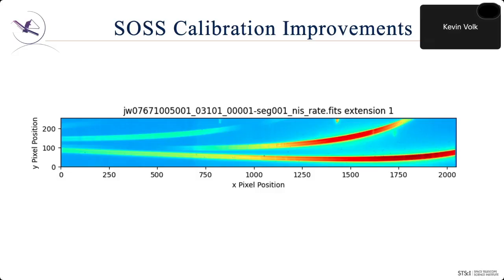This is what the spectra look like when you take a spectrum in this mode, just to show you. We've got several spectral orders on our detector. The first order is the one at the bottom, so that covers most of the wavelength range. Then order 2 is up above it and covers the short wavelength range from about 0.8 to 0.6 microns. And in this case, you can actually see, if you have good screen resolution, H alpha is here. So then you have more lines around 1 micron because it's an A-type star. We also have order 3 here. You've got minimum in these higher orders because of the blaze of the grism. So this is in order 2, the signal just about goes down to 0. But that's redundant with order 1, so we don't care. There's also a very faint order 4 up there, which we don't bother to try to deal with.